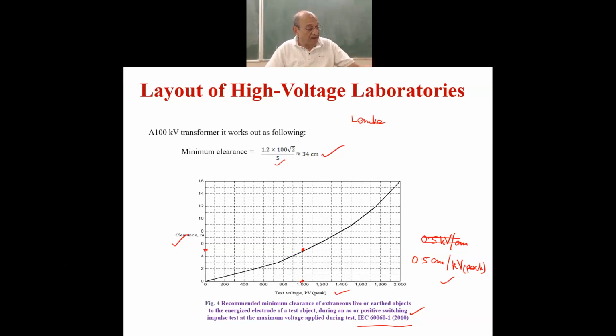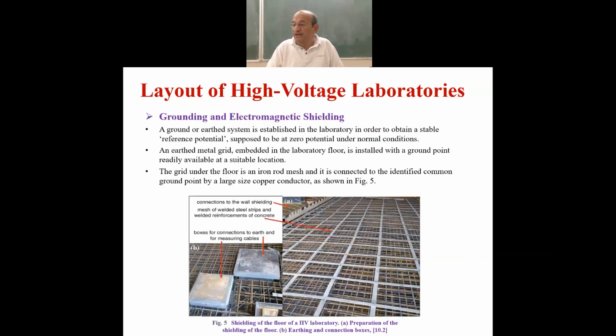So, I'll just show you grounding. Electromagnetic shielding is provided in the laboratories. The whole floor is laid with iron mesh, and there are places where the mesh is grounded, and a ground or earth system is established in the laboratory in order to obtain a stable reference potential, which is supposed to be zero. If it acquires some voltage, that is not desirable, so it is grounded, and it should be zero potential under normal conditions. When current is flowing through the ground, it may temporarily acquire some voltage.